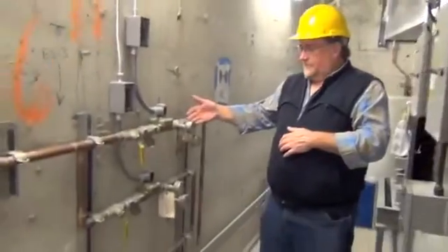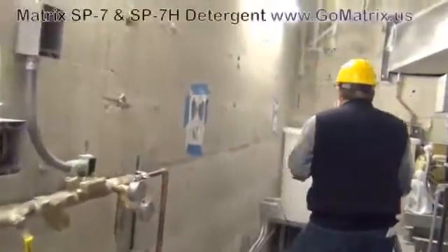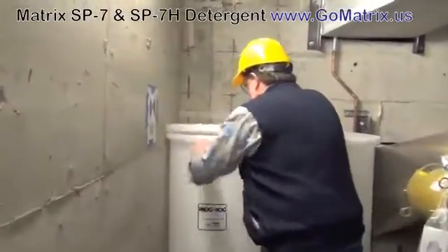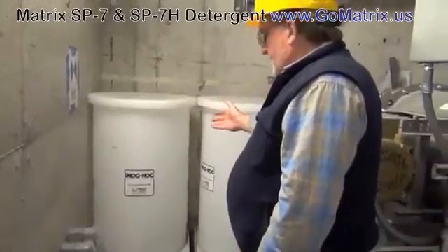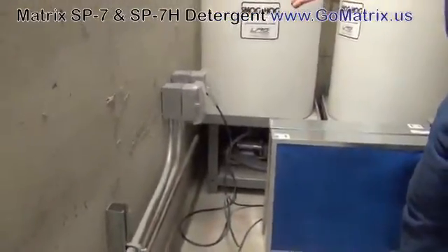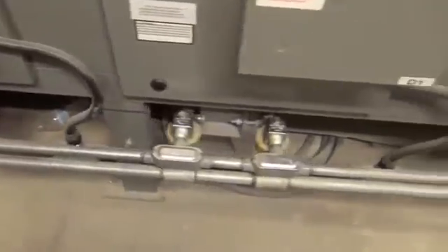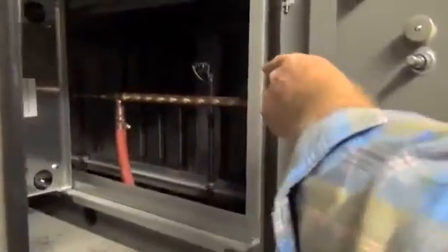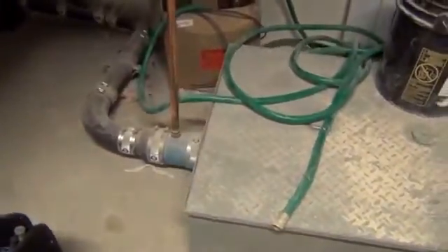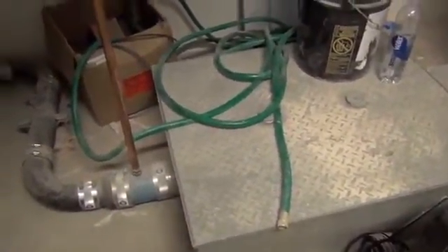Here we have our main solenoid valves and pressure gauges. Detergent tanks and detergent pumps, which are controlled by the main wash panel through these outlets. It's a series of solenoid valves that on a time basis provide for the flow of water onto the precipitator cells through these nozzles in these wash manifolds. Wastewater from the automatic wash process is collected through drains in the floor of the Smog Hog cabinets and then is transported through these pipes to a rated grease interceptor prior to being disposed of in the sanitary sewer.